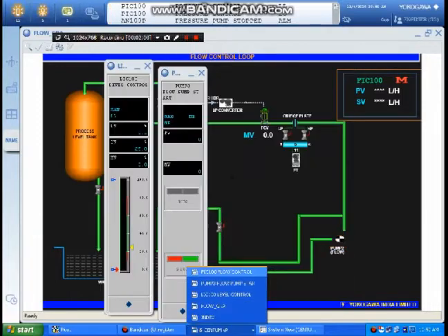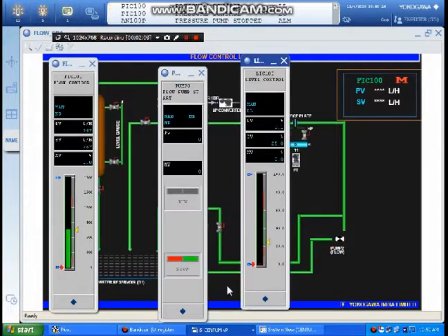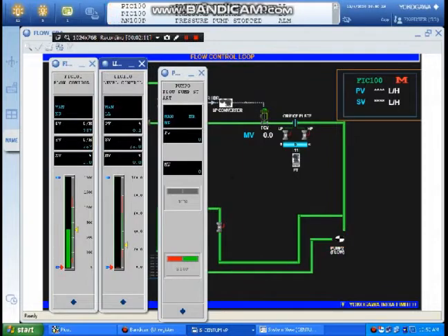When we use this, we can see that the flow pump, we are switching on and off, and we have flow control as well as level control. For the level control system, instead of changing from manual to auto mode, we will be moving to cascade mode. Flow will act as a normal PID mode. This system is your secondary loop, level is our primary loop. So the primary loop for a cascade control system here is level, and the secondary loop is flow.